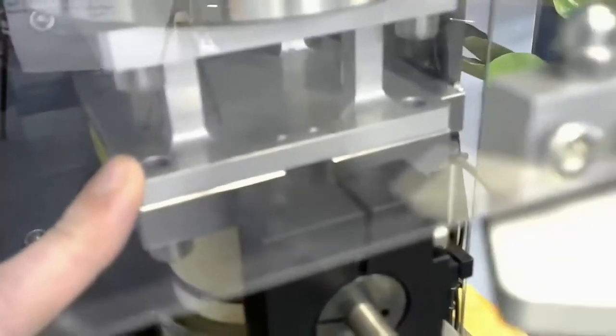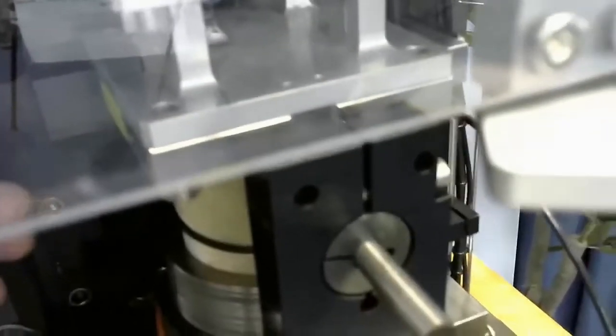We have 3 load cells: an axial load cell just in here on the vertical carriage, and our unique primary shear load cell design a little bit further up. This sits above the sample, so we don't see any of the friction build up in those lower horizontal linear guides. We also have a secondary shear load cell just at the back here. This is a good reference load cell, but it's also used to protect the machine when those samples are installed.